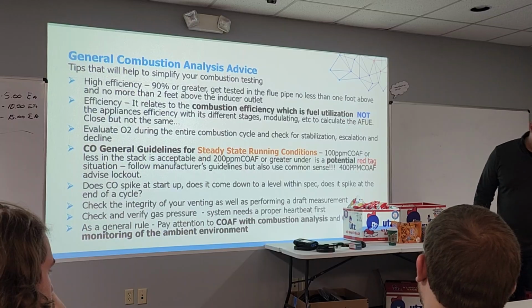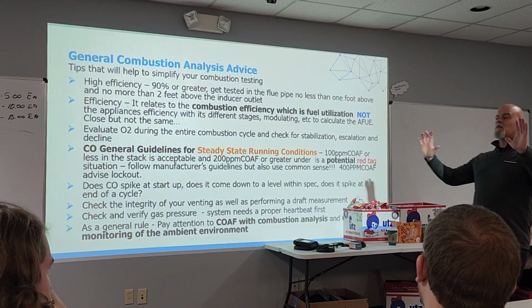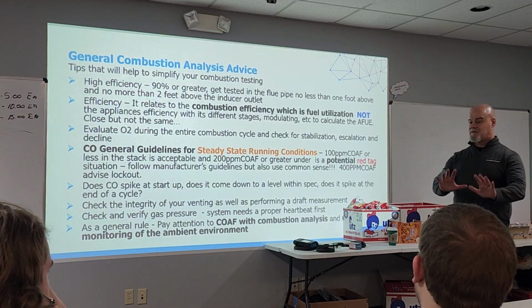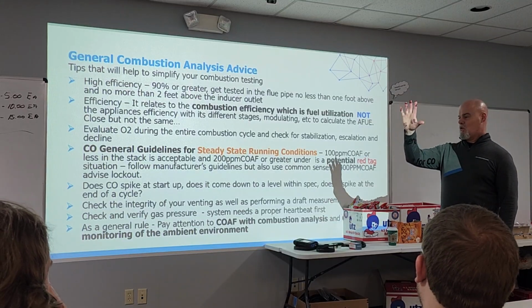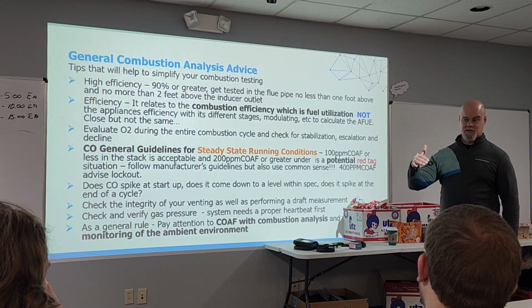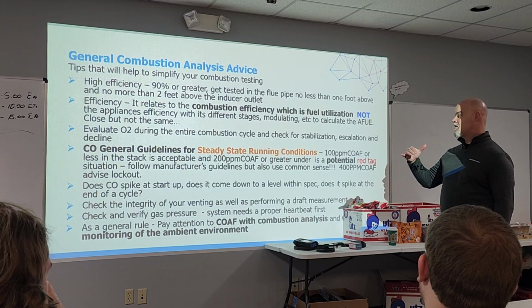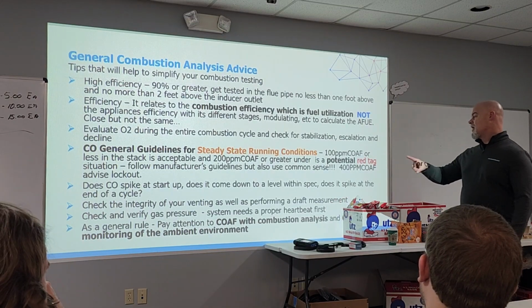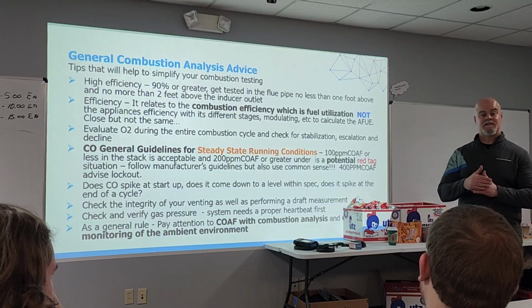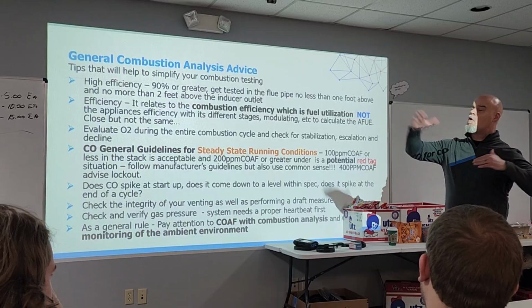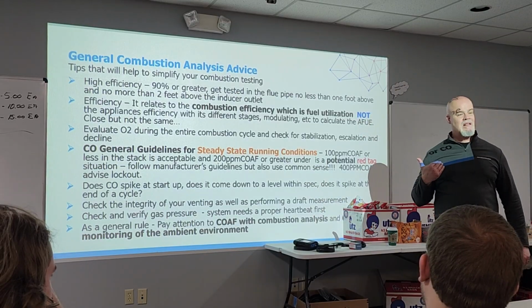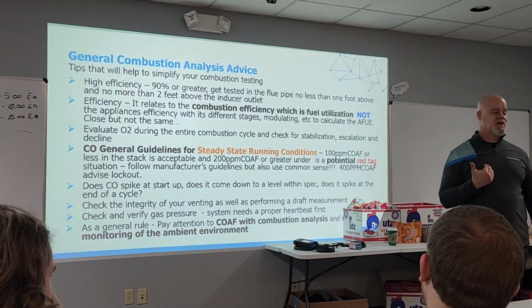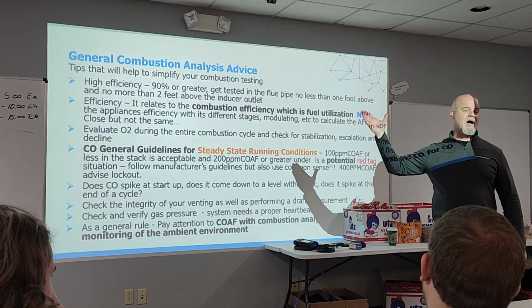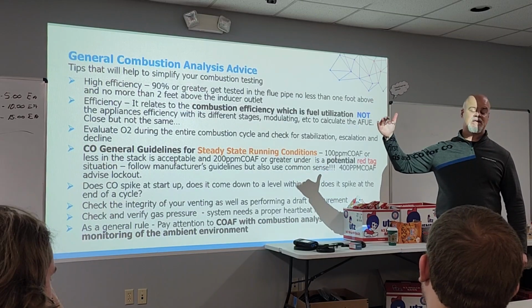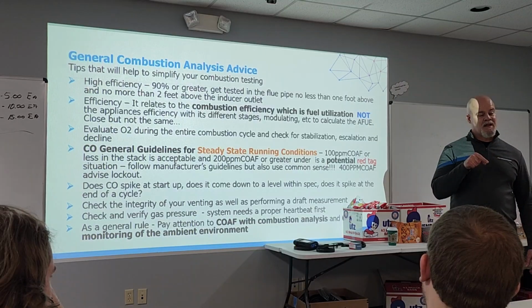So what I don't want is, when you're evaluating a system, I don't want you off your heels. You don't have to do that. Take a second, watch what it is doing, look at its behavior, see if you see any tells or characteristics that show you what you need to go after. For example, if it spikes at startup and it's a condensing system and it goes over 1,000 ppm, which we're going to get to in a second in diagnostics, I am not letting you get into steady state, nor am I letting you get into shutdown. If I get over 1,000 ppm, because that's a high threshold for me, that's the threshold that the industry sets, I'm shutting you down.